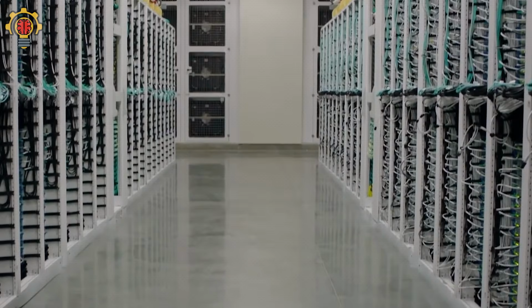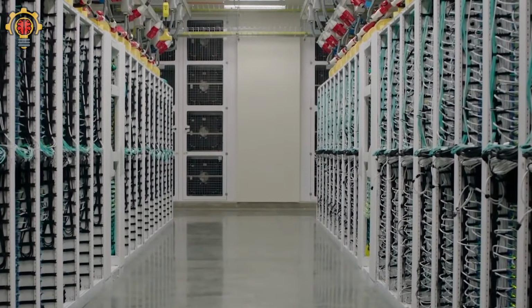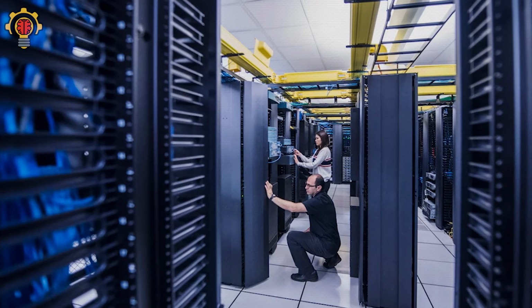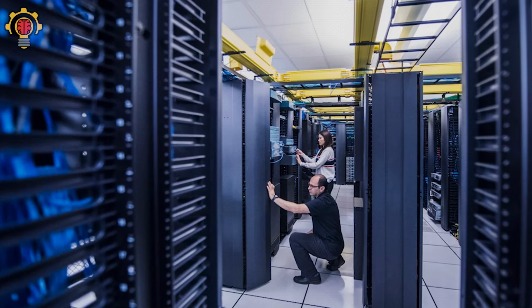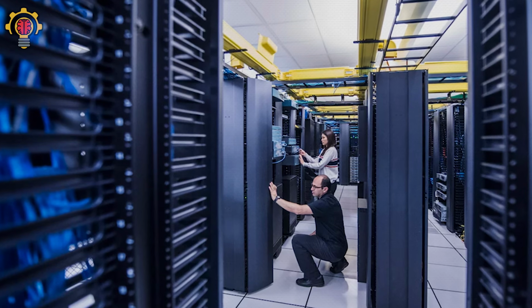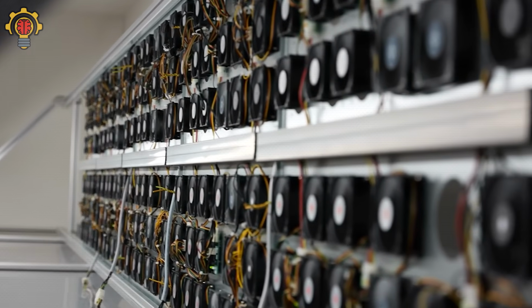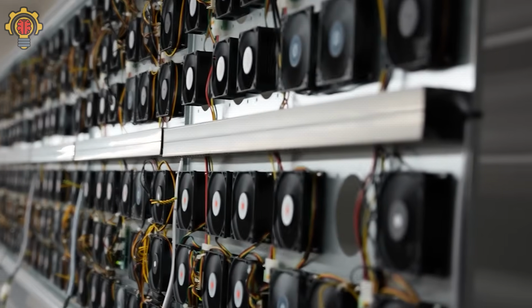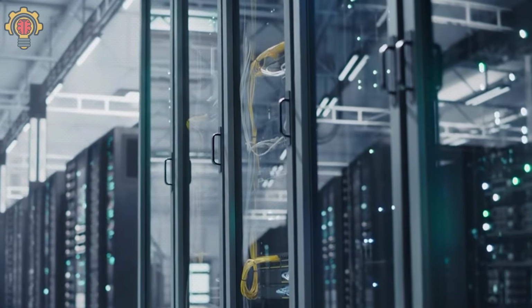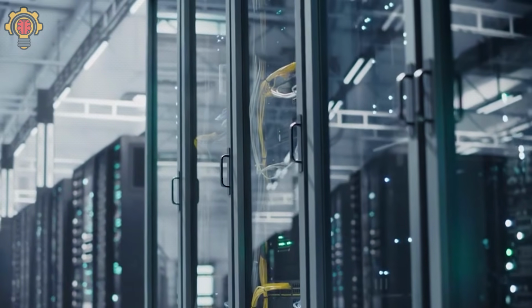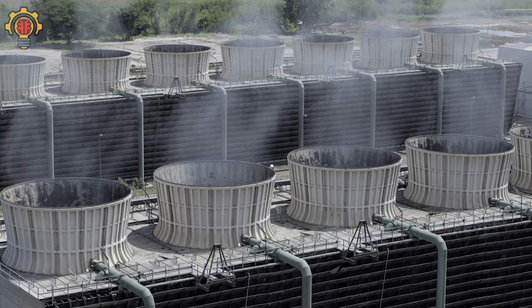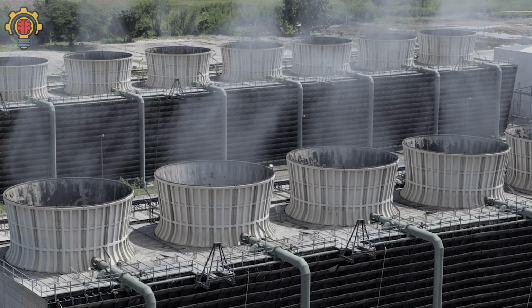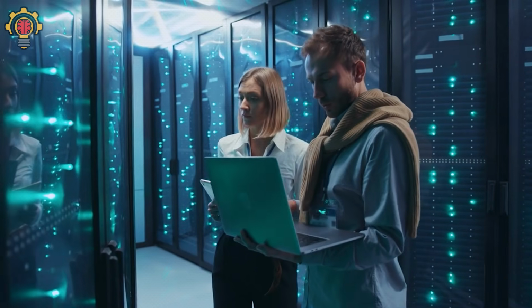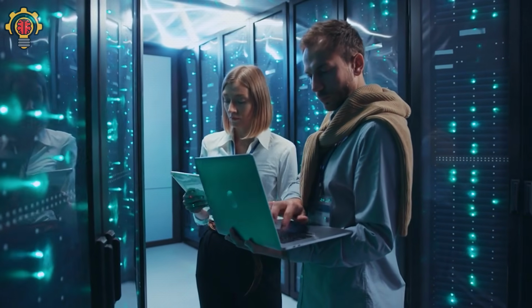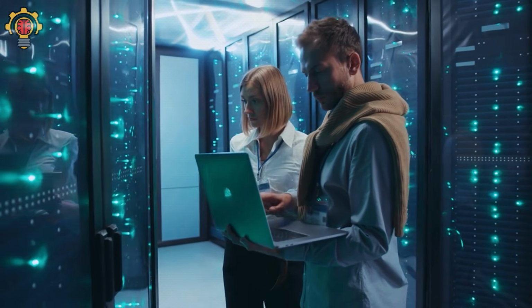Instead of placing cooling units around the room, these systems are installed directly between server racks, much closer to the actual heat source. They pull hot air from the hot aisle, cool it immediately, then push cold air back into the cold aisle. Because airflow paths are shorter, cooling becomes more efficient, while fan energy usage drops significantly. And this matters because not every rack produces the same amount of heat. One row may contain simple networking equipment, while another row contains powerful AI processors generating enormous thermal loads.